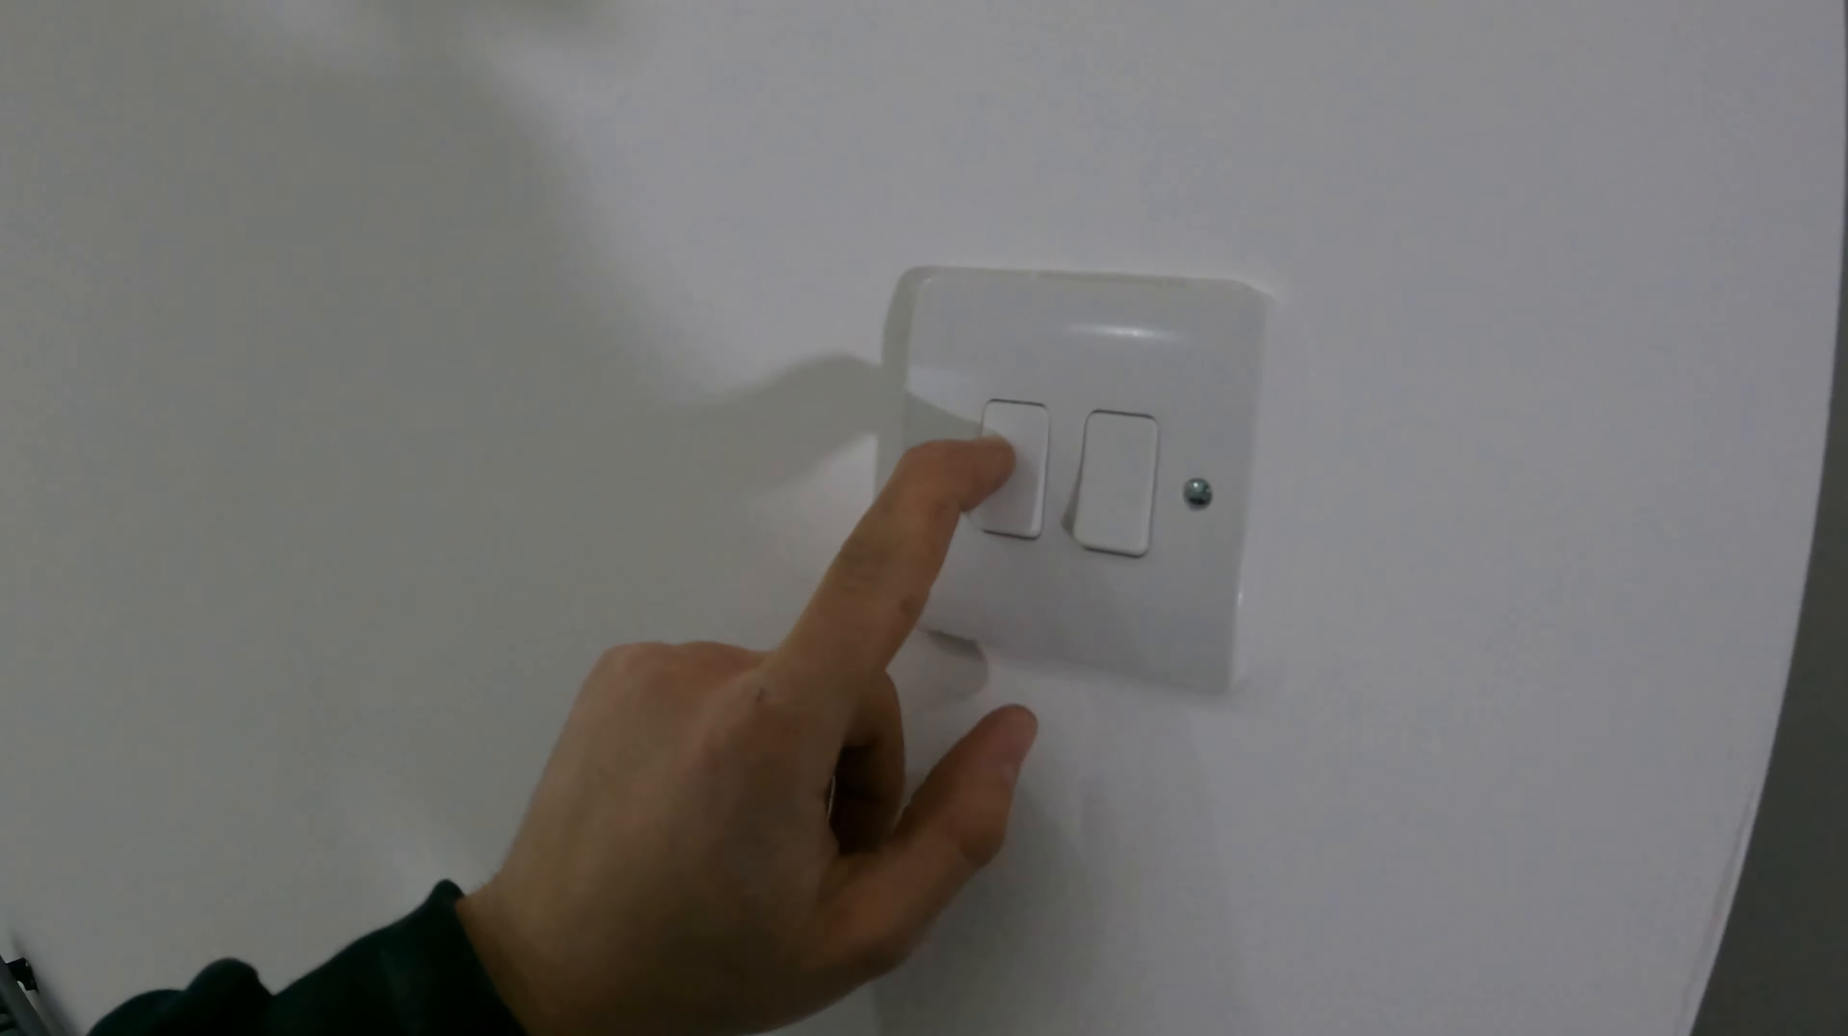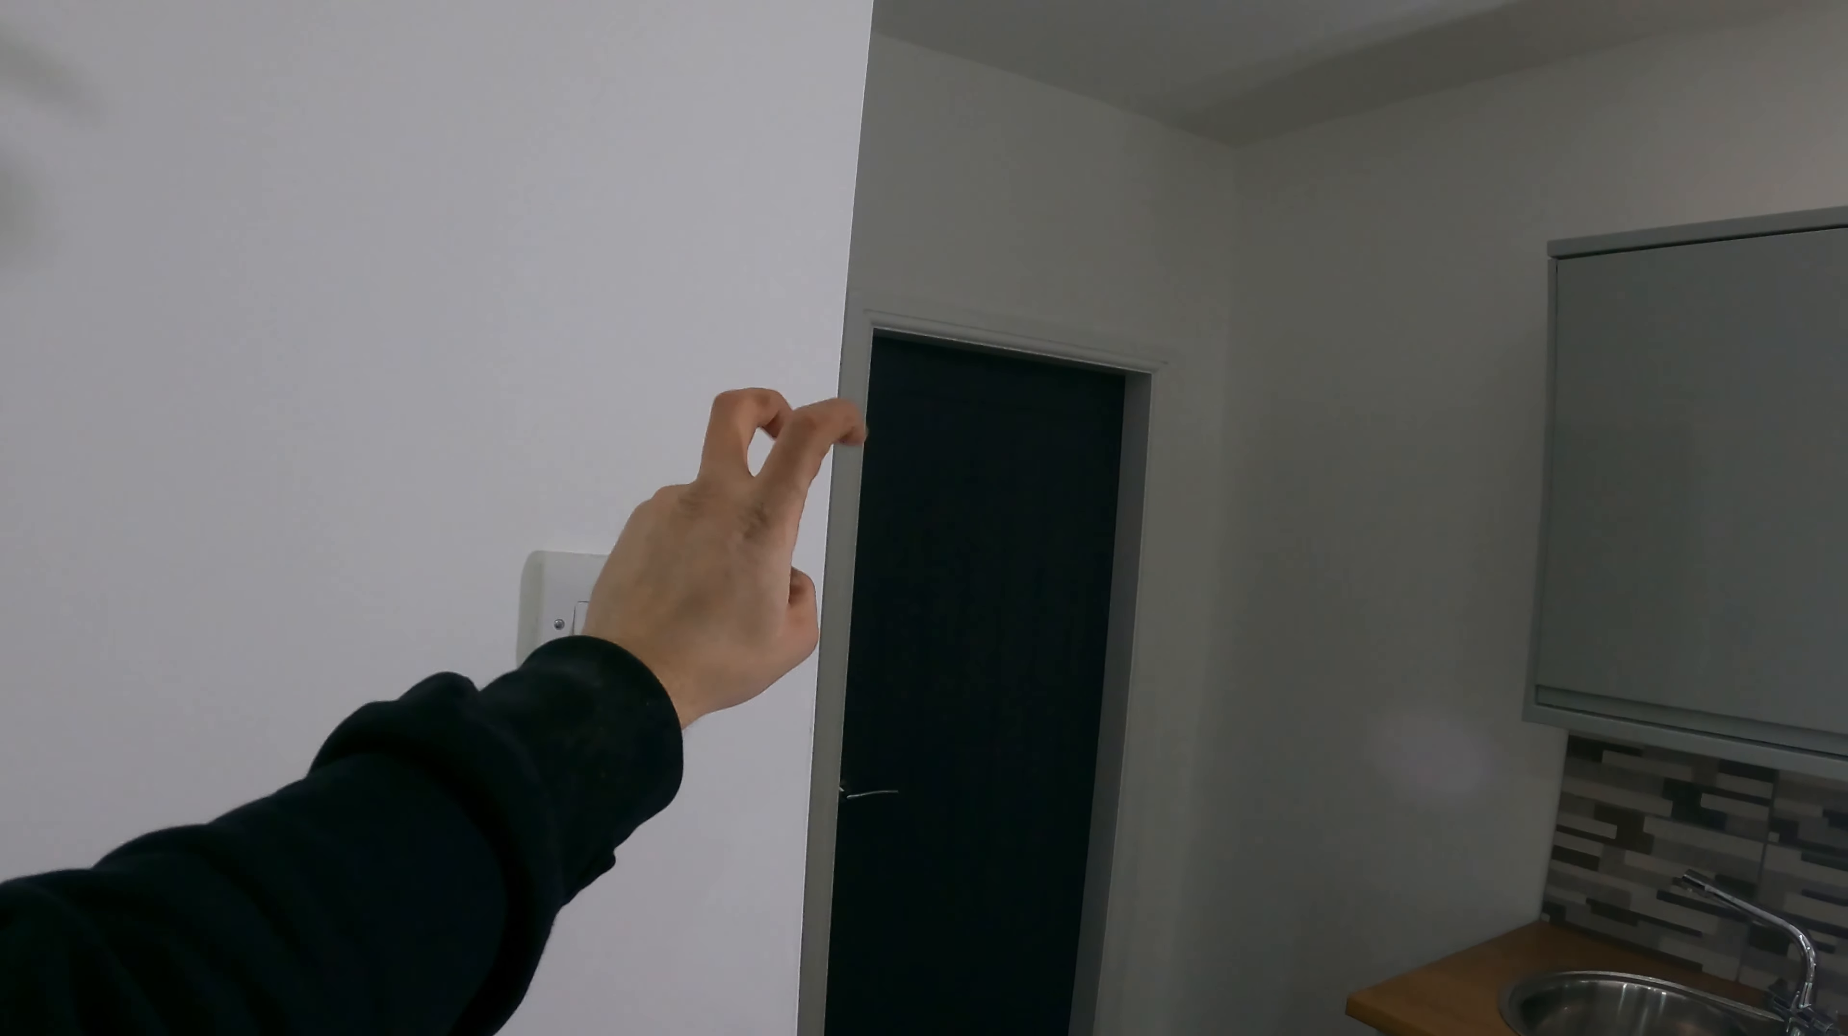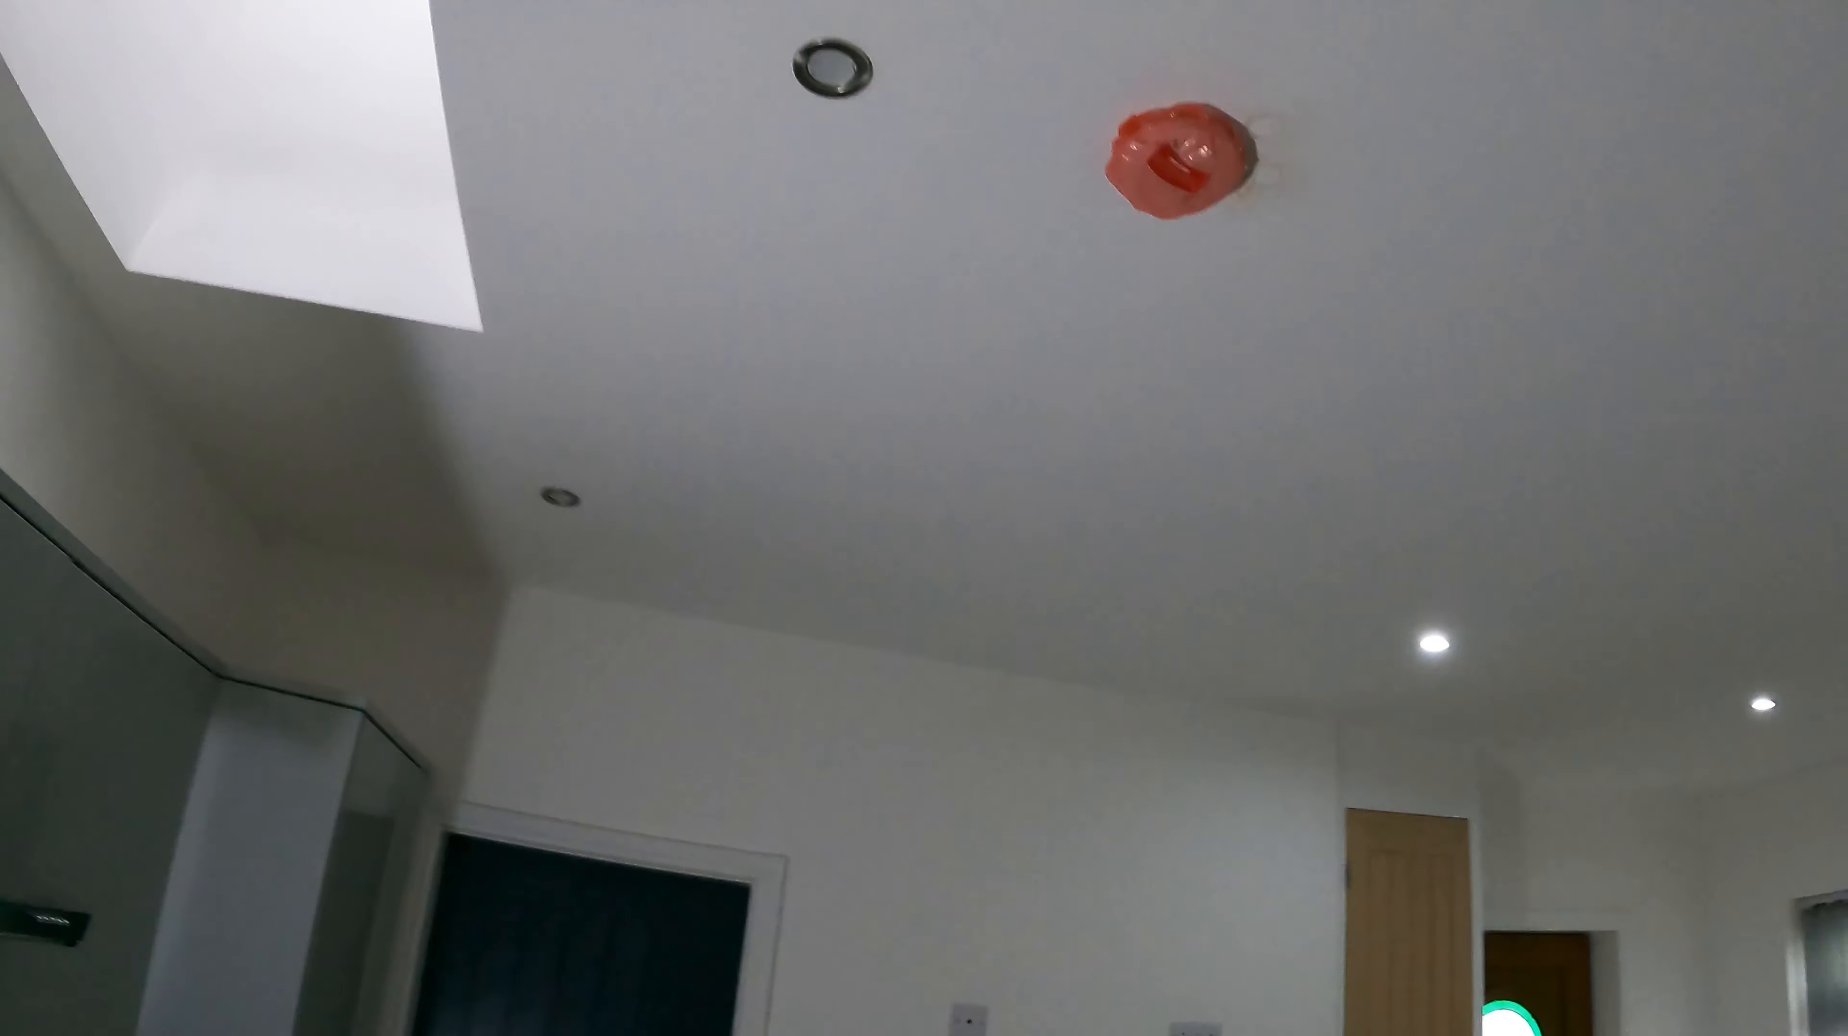So we've already got a cable in there that we don't need. We're going to disconnect one of them and hopefully use it to feed that, and we'll then connect it to the permanent side of this switch. And then we'll have the other leg of his ring to do them three lights. Hopefully it goes to the smoke detector first—that'd be perfect. But we're going to have to spell it out, test it up and whatnot, find out.